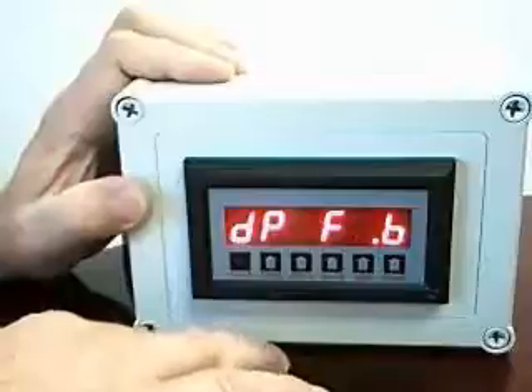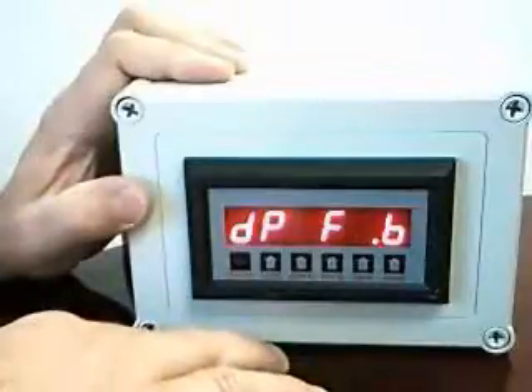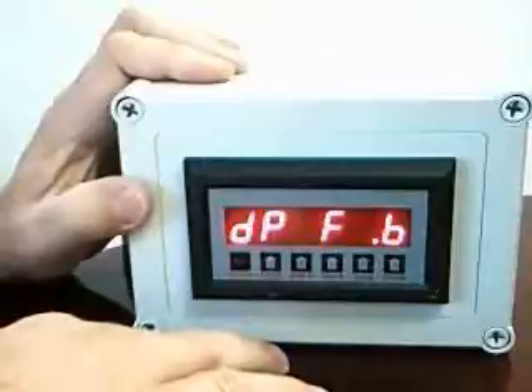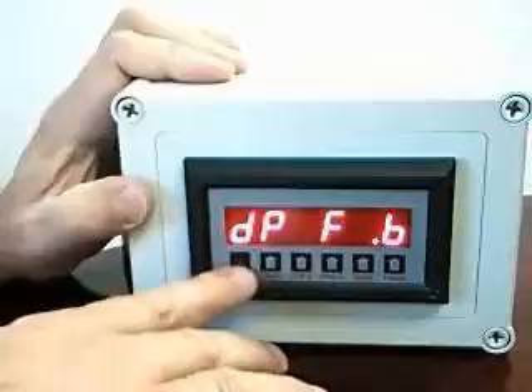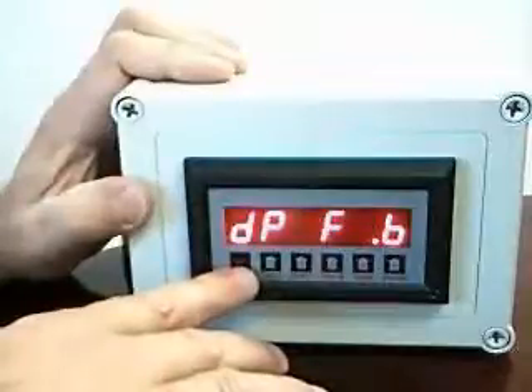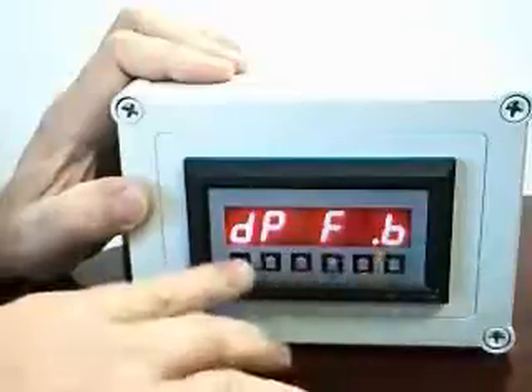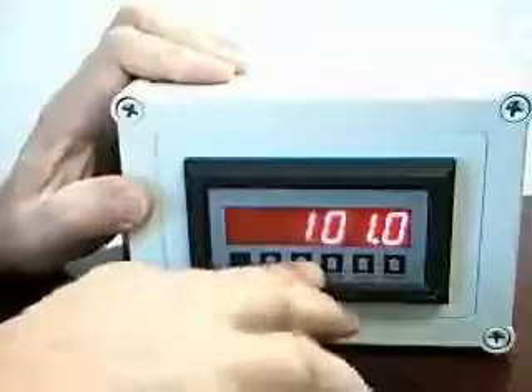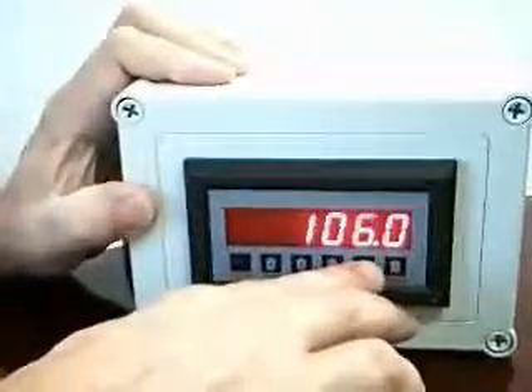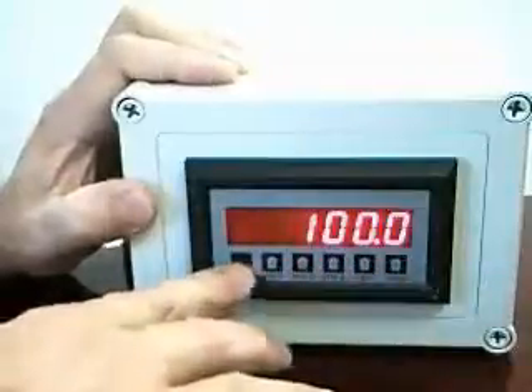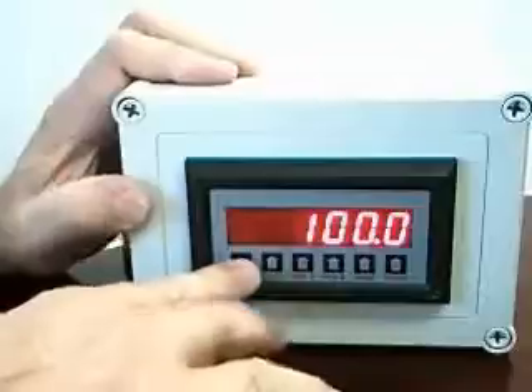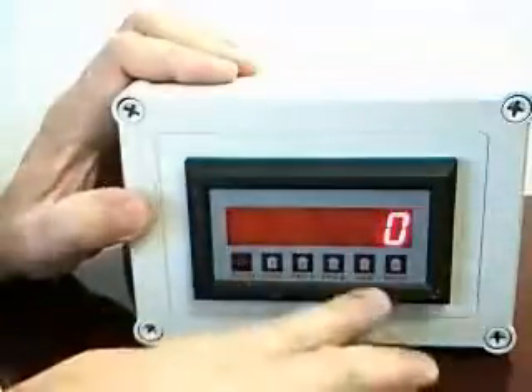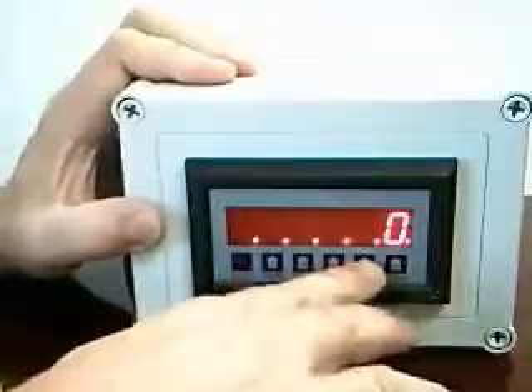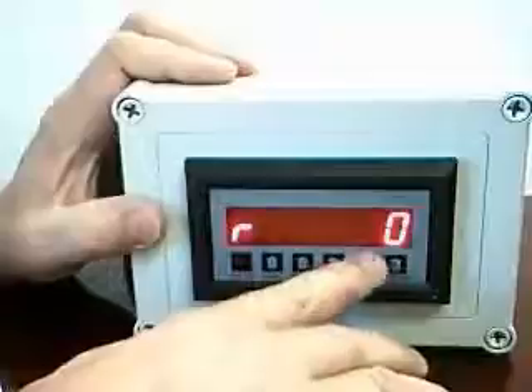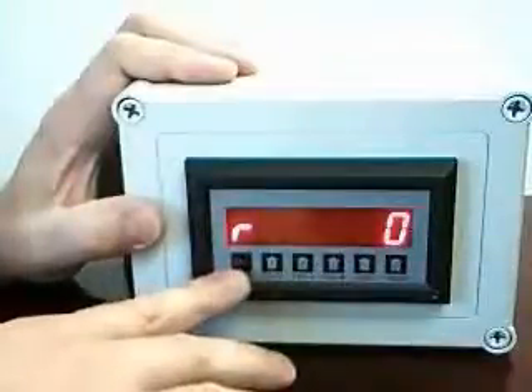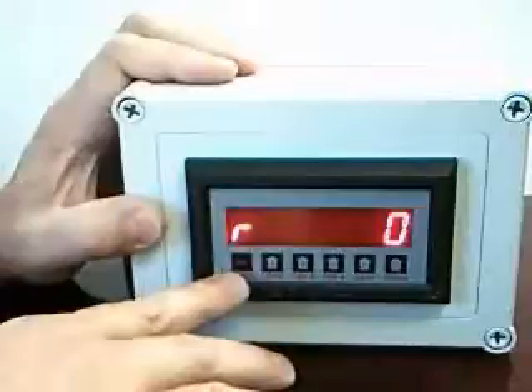In this case, since this is a 2-channel instrument and there is an auxiliary totalizer, I'm going to enter the same calibration constant in the B factor to the same resolution. So once again, I'm going to show 1 digit, and by pressing Enter, I'm going to enter the same calibration constant in the second channel. After that's displayed, I'm going to hit Enter, and at this point it's going to return me to the run mode. Now you may remember, in the run mode you can see several totals as well as the flow rate. And I'm going to leave this displaying the rate so we know each time we return to the run mode.